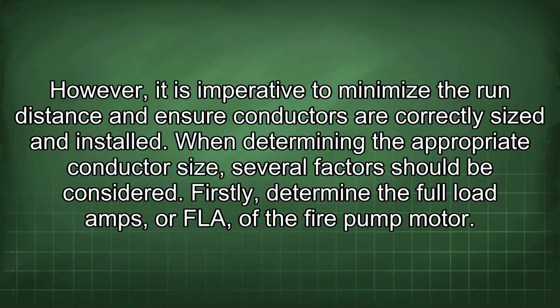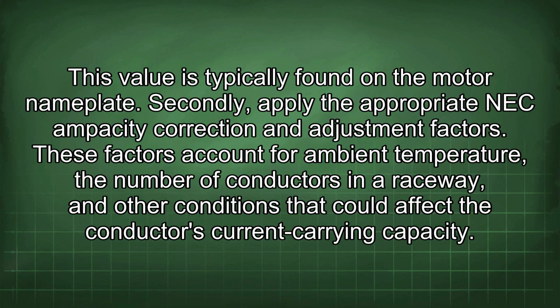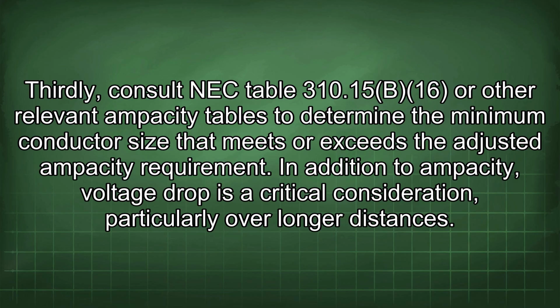When determining the appropriate conductor size, several factors should be considered. Firstly, determine the full load amps, or FLA, of the fire pump motor. This value is typically found on the motor nameplate. Secondly, apply the appropriate NEC ampacity correction and adjustment factors. These factors account for ambient temperature, the number of conductors in a raceway, and other conditions that could affect the conductor's current carrying capacity. Thirdly, consult NEC Table 310.15(B)(16) or other relevant ampacity tables to determine the minimum conductor size that meets or exceeds the adjusted ampacity requirement.